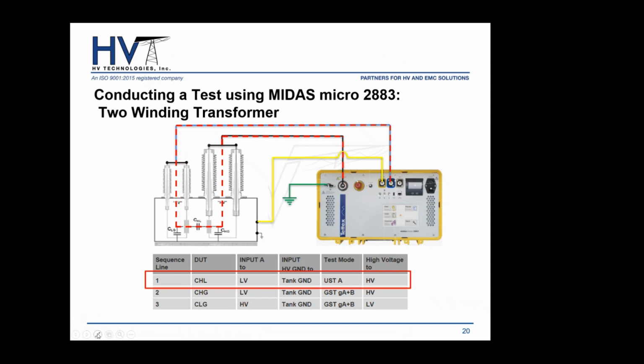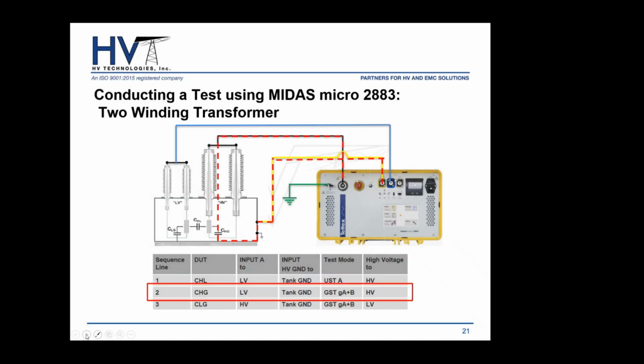Similarly, for the high voltage to ground, we'll maintain our connection on the high voltage and low voltage as previously described. But in this mode, we'll choose grounded, since we want to get the high to ground, the GST mode, and we'll use the guarded A and B. Guarded A and B will basically take any signals that are generated to these measurement channels and take them out of the measurement circuit. And there we'll have our high voltage to ground capacitance and tan delta.